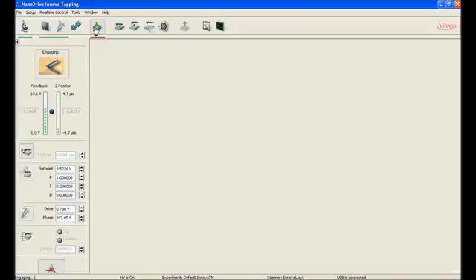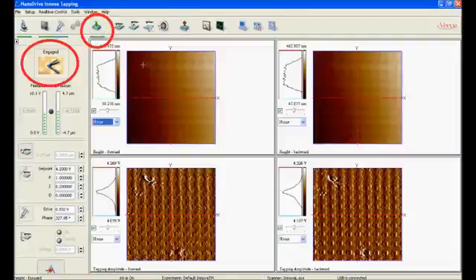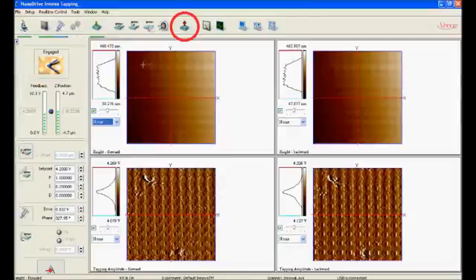In this example, I forgot to adjust the set point, and there seems no way to stop this bad approach from happening. To trick the software into stopping the auto approach, I changed the set point to a value higher than the feedback. This tricks the software into thinking the tip is already engaged and canceling. The software signals an engaged tip with this message to the right. This is also indicated by a green bar beneath the Engage button. To disengage our tip from the surface, we need to click this button. This is the only way you should ever lift a tip from the surface.